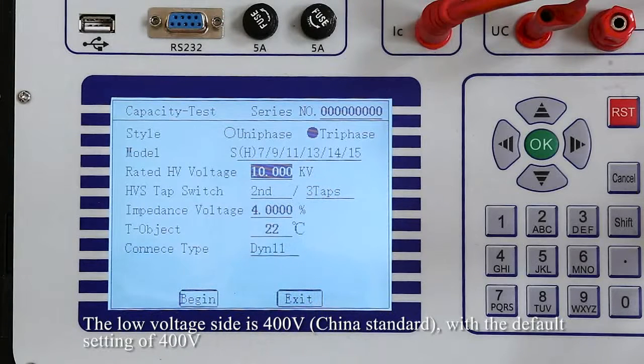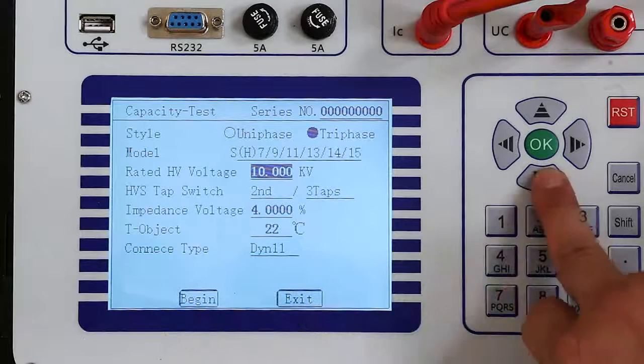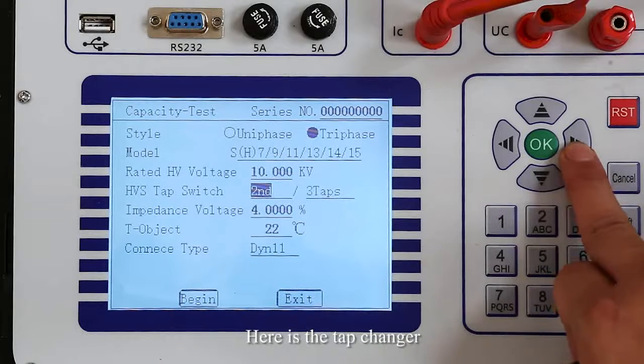The low-voltage side is 400V with the default setting of 400V. Here is the tap changer.